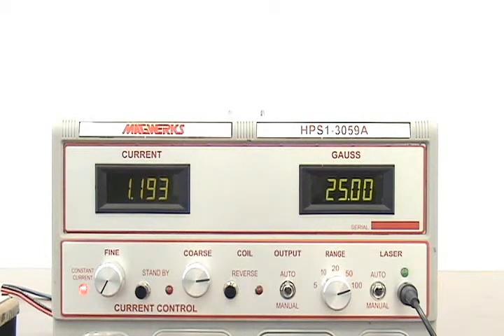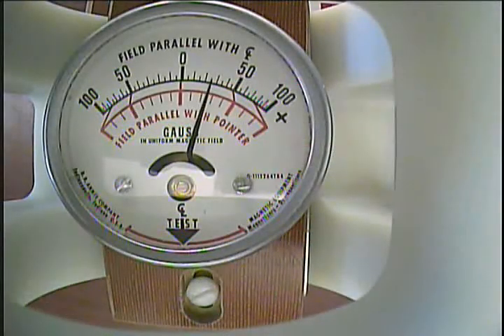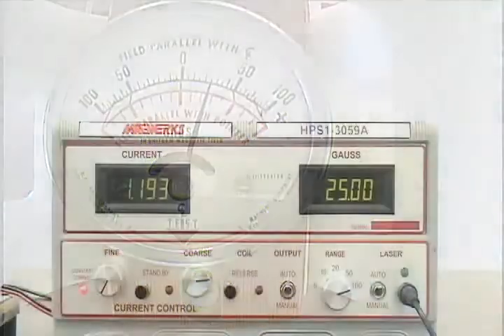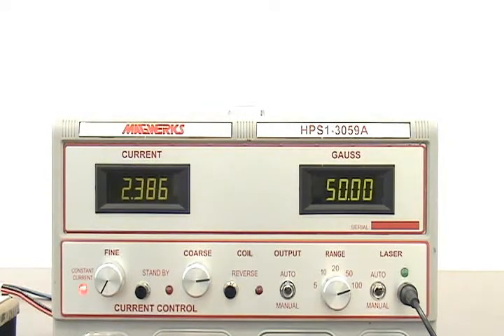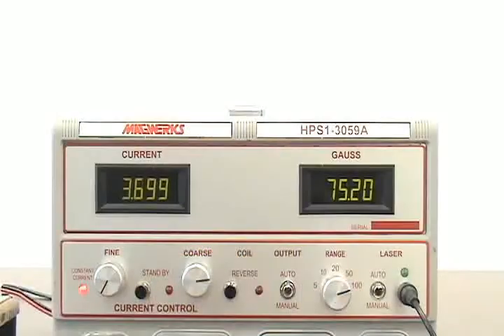The power supply starts. At 25 gauss, the magnetometer reads 25 gauss — first test point, good. Second test point, 50 gauss — the magnetometer reads 50. Now 75 gauss check: the magnetometer reads 75, and the power supply reads 75.